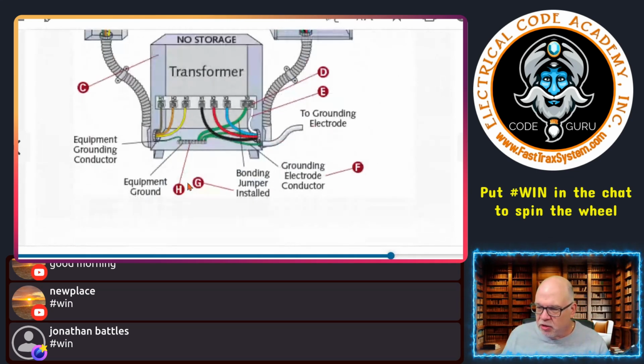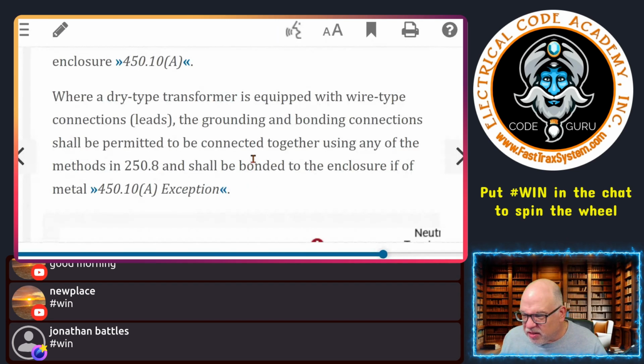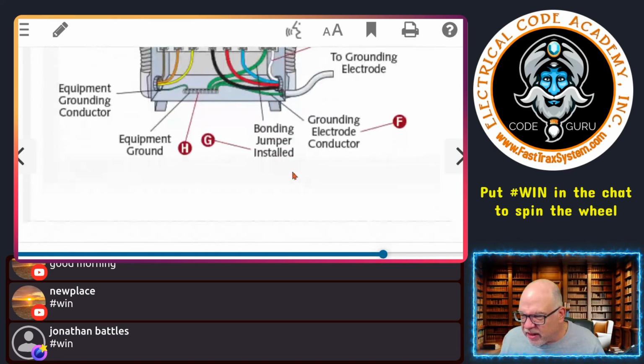So right here, this connection is connected over to here through this system bonding jumper. All of that is connecting to the grounding electrode conductor right here. So it makes all of this intimate. That's why it's so important to size the system bonding jumper properly. So all these connections are intimate, and then it goes from here. You see that? Now look right in here. I don't know if I can zoom in on this. Let's see if I can zoom in a little bit so you can see it.